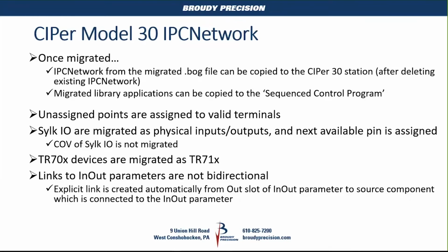Granted, you're going to want to go back in then and double check your IO assignments, make sure everything's assigned the way you expect it to be within the CIPer 30, and just go through and make sure everything looks good. All of those migrated Spyder applications, all the components within the Spyder application, are going to go underneath the sequence control program. Because if you remember, in the CIPer 30 IPC network, you have a sequence control program and you have an event control program.